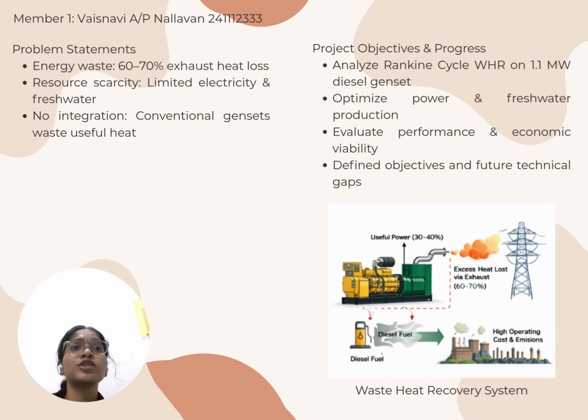Based on the literature review, this study addressed three main problems. First, there is significant energy waste due to exhaust heat losses. Second, many remote and island regions face limited electricity supply and freshwater scarcity. Third, conventional diesel generator systems do not integrate waste heat recovery efficiently. Therefore, the objectives of this project are to analyze the operating principles of the Rankine cycle-based waste heat recovery system applied to a 1.1 megawatt diesel generator set, optimize additional power and freshwater production, evaluate key performance parameters, and assess the economic feasibilities of the system.